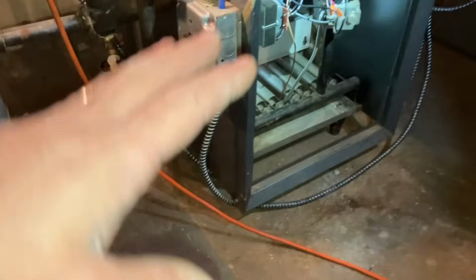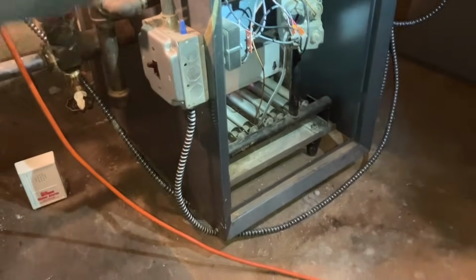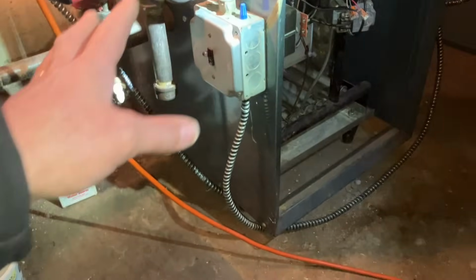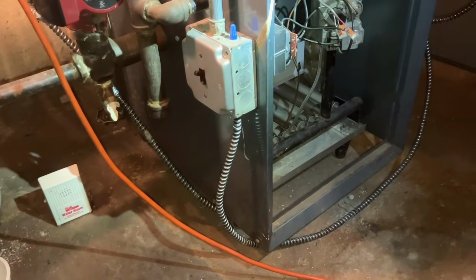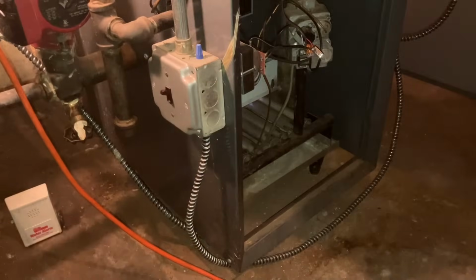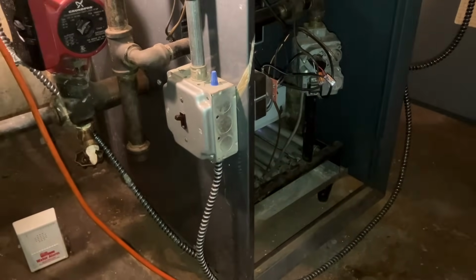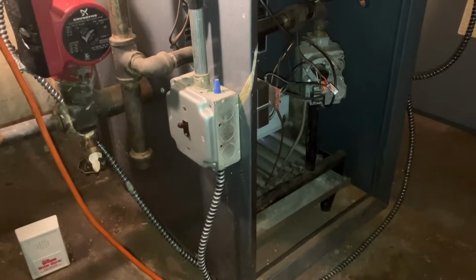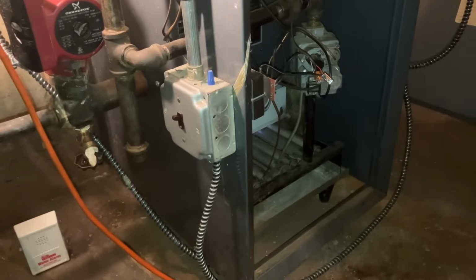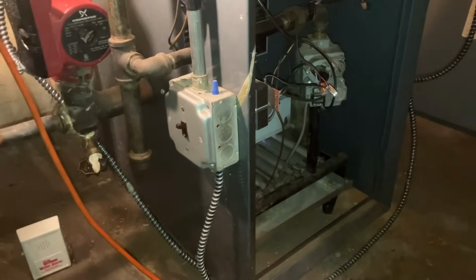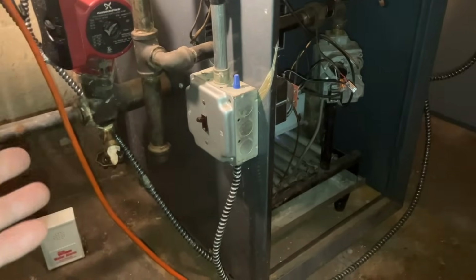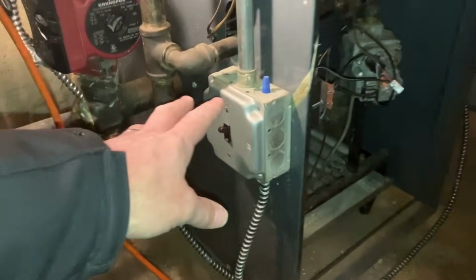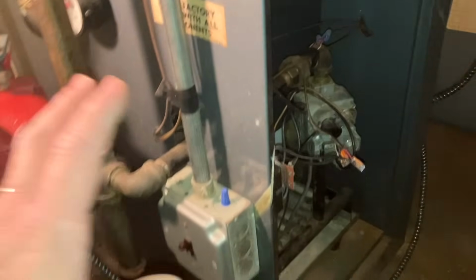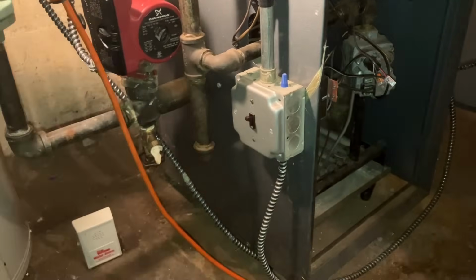Yes. And if we were to, let's say, just remove the wire for the, I don't want to go into there because, again, this is X amount of years old. So unless I suspect a problem, I'm not going to go into it. So you had asked earlier, if during a tune-up. Now, there are tune-ups that a lot of plumbing and HVAC contractors do that unfortunately are not worth anything. And there are tune-ups by my company where we spend, on this system, an hour and a half a year. Would we have found this wire being loose in there? Unless I suspect a problem, there's no reason to go into that switch, right?